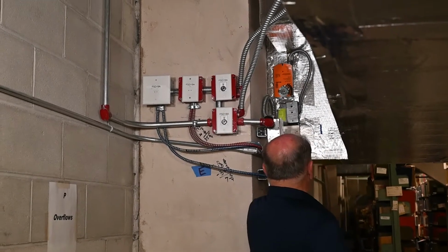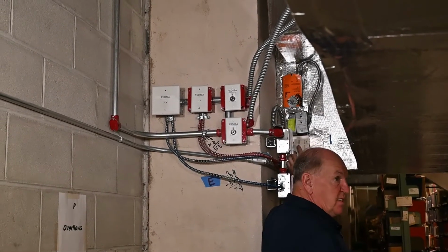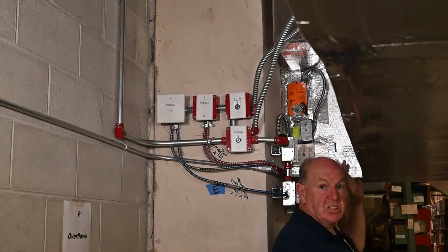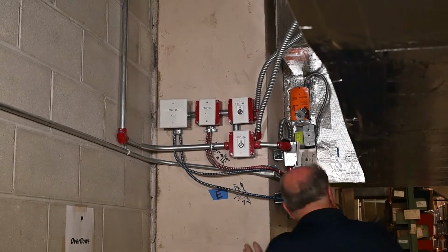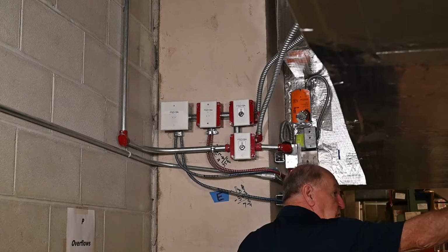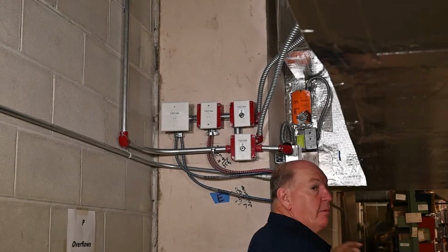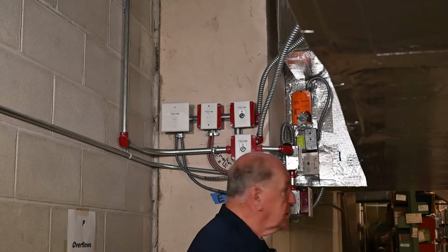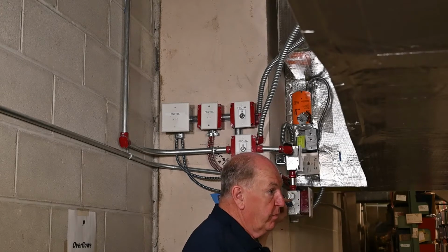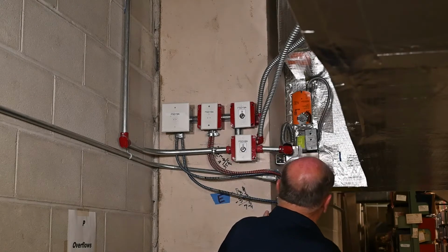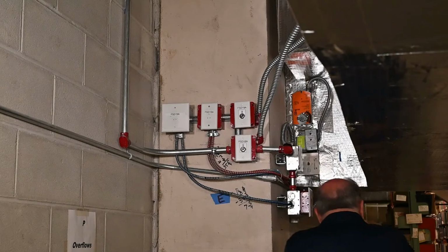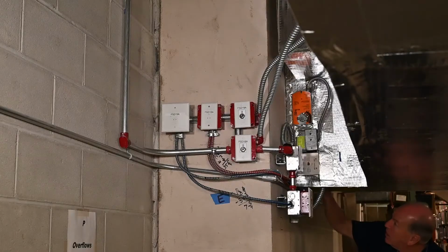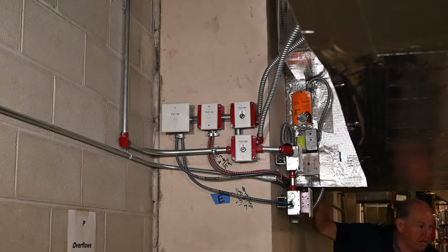There is a test switch here. Usually it stays in normal. And if the duct smoke goes off, there's a duct smoke detector here. If that goes off or the fire alarm trips, it will actually close this damper. And you can see the shaft. And also, there's an access door right here where you can see the damper to verify that it hasn't slipped on the shaft.